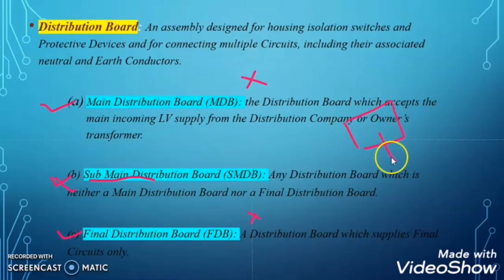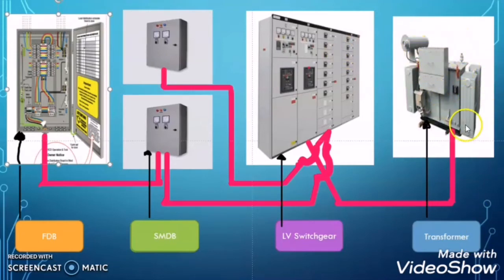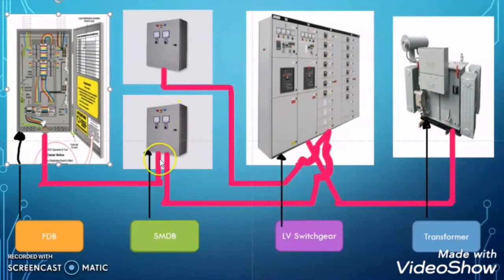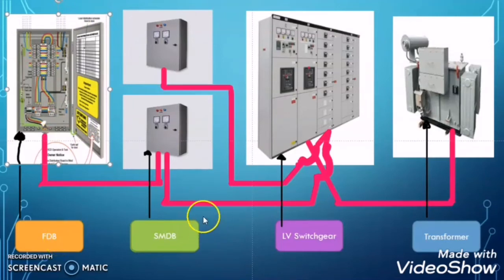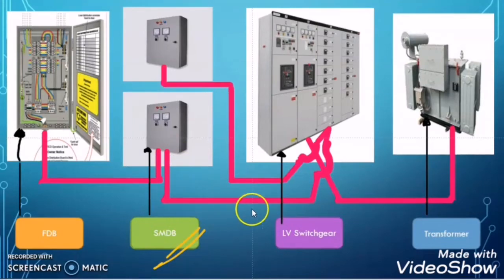The sub-main distribution board should not take power directly from the transformer and should not feed the final circuits. In our example, you can see there is a transformer which is directly feeding the main distribution board (MDB or LV switchgear). The outgoing of the MDB feeds the SMDB, and the SMDB feeds the FDB, which in turn feeds the final circuits directly supplying power to the loads. The sub-main distribution board is only the mediator between the MDB and the FDB.